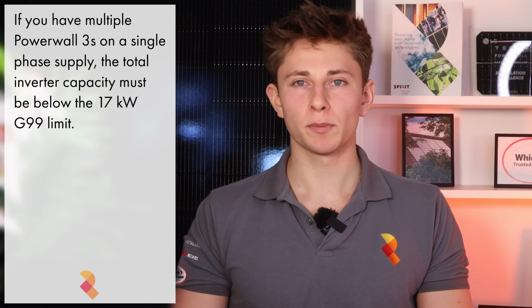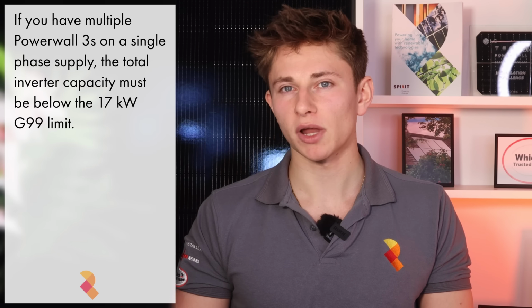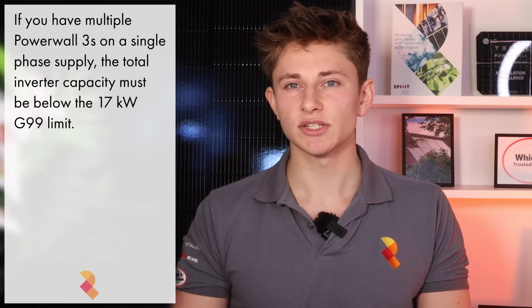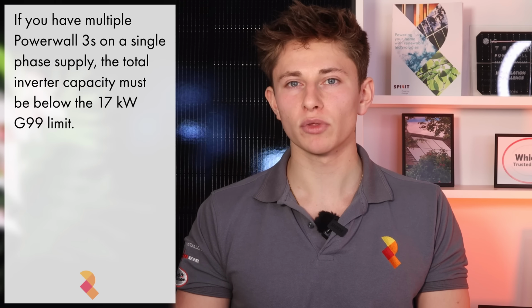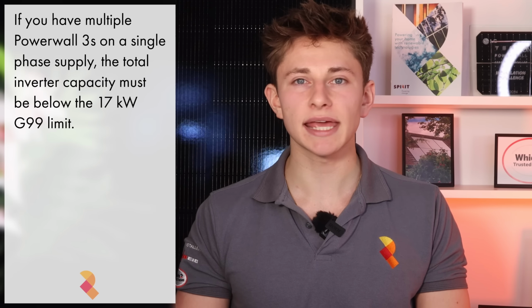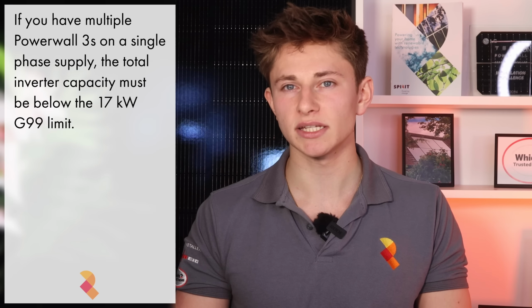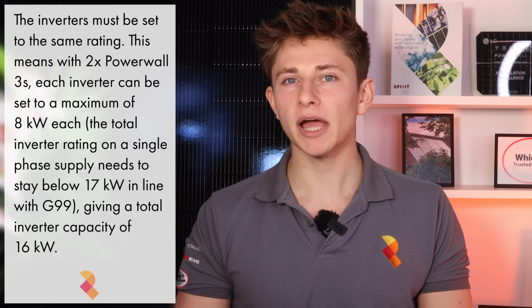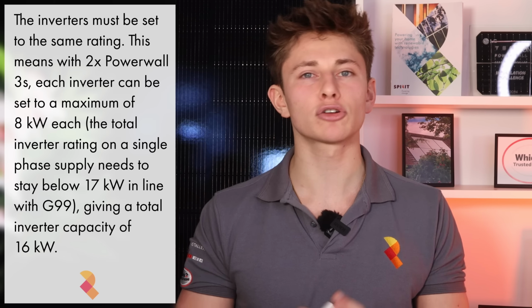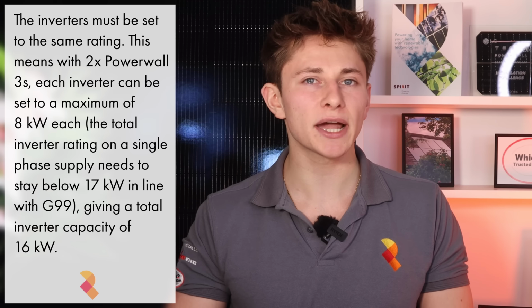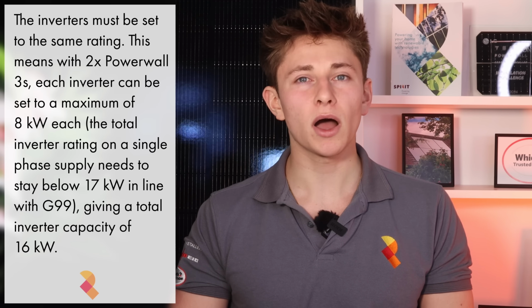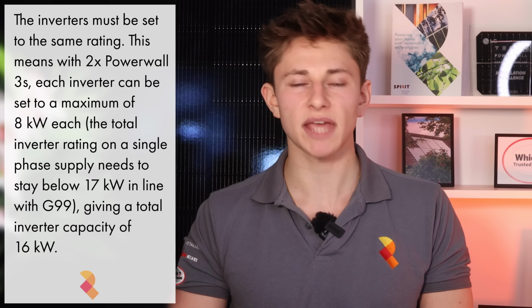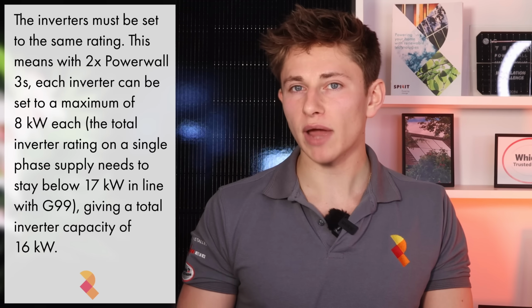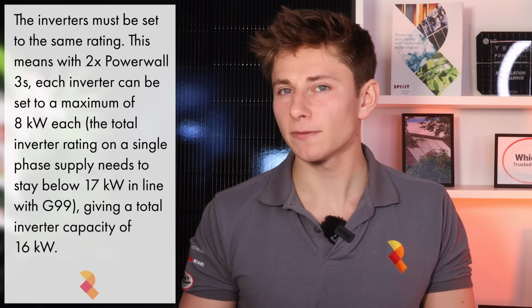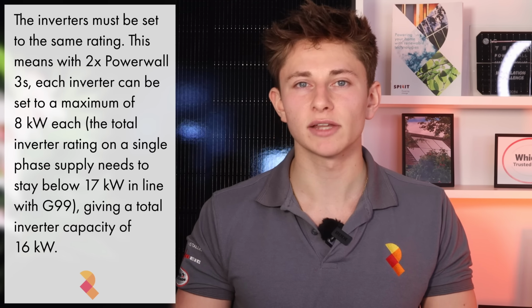If you do get multiple Powerwalls installed on a single phase supply, then the inverters within the systems will need to be downrated to ensure that the total installed capacity stays within the 17 kilowatt G99 DNO limit. The Powerwalls must be set to the same rating across the board. So if you have 2 Powerwalls on a single phase supply, the highest rating that they can be set to is 8 kilowatts each. If you have 3 on a single phase supply, then the most they can be set to is 5 kilowatts each.